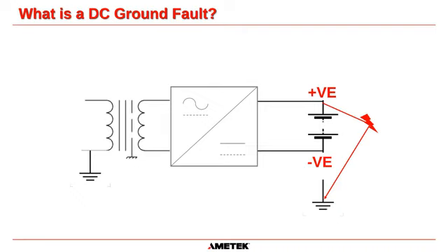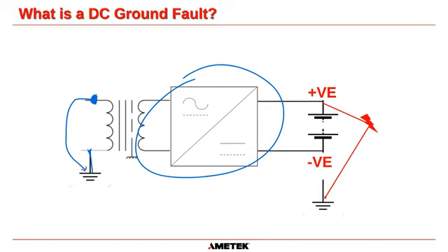Because remember, in your house, this is irrelevant. You don't have an isolation transformer. The neutral is connected to ground. So if you touch this positive point here and somehow you get to the ground in your house, now remember, your concrete in your house or the frame of your house, if there's any metal in it, has to be connected to this ground connector here. So if you do get a shock on your wooden floor, it must mean that your wooden floor is not giving you complete isolation from this ground circuit here. So that is why you would still get an electric shock.